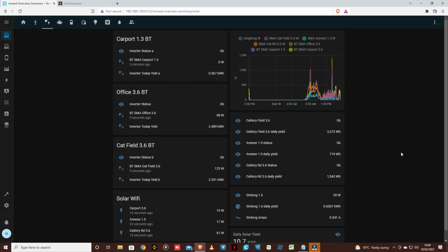That will enable you to see that you could have cloud cover, or you could be disconnecting on one of your SMA units, you don't know about it, and then suddenly reconnecting 4 or 5 hours later. You'll want to know why. Is this a communications fault? Has the inverter picked up a grounding fault? All of these kinds of things. So it's leading you into a situation. Okay.